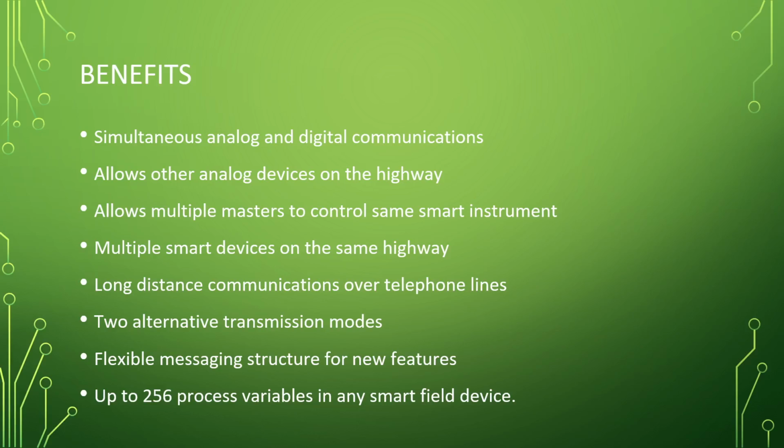This does allow other devices to use the analog highway, basically, so that's kind of nice. Multiple masters, that's a big one. Oftentimes with these things, it's a single master device, and that's all you're allowed to have. Once you start getting multiple masters, that's when the fights begin, because it's like, do I listen to this one or do I listen to that one? And who's communicating? And when are they communicating? So the fact that this does allow multiple master devices is really quite a good thing.